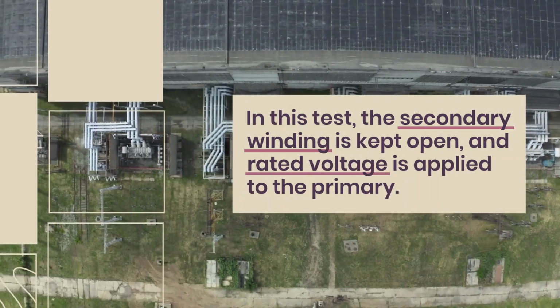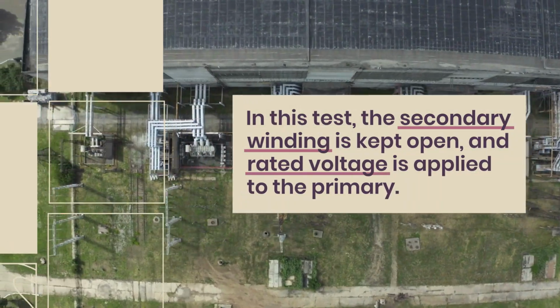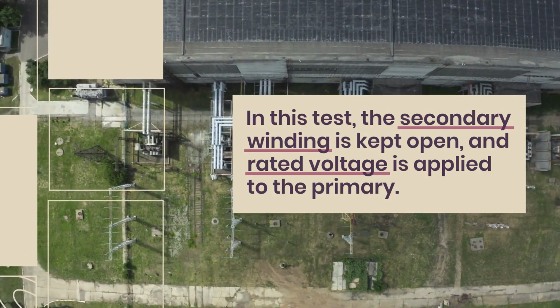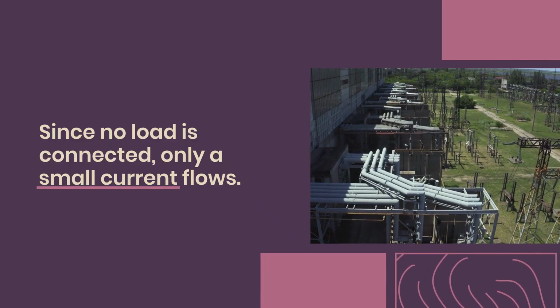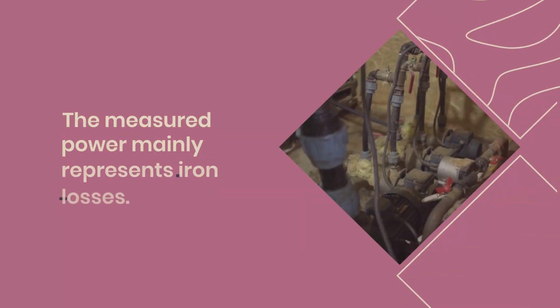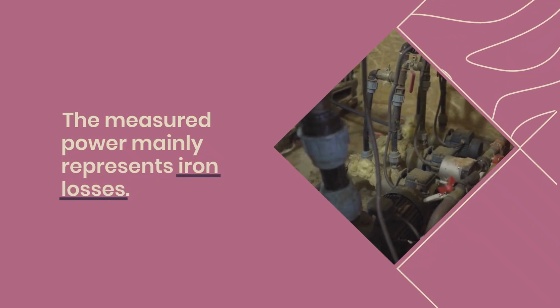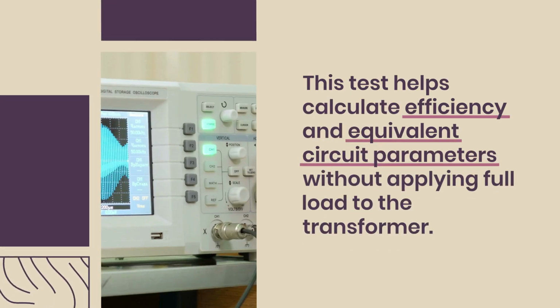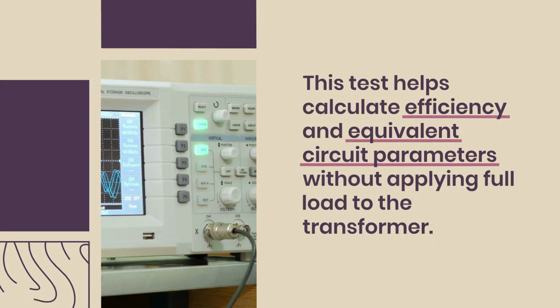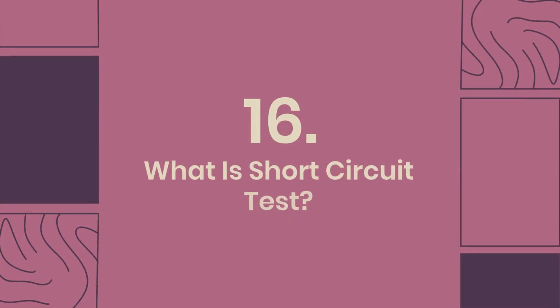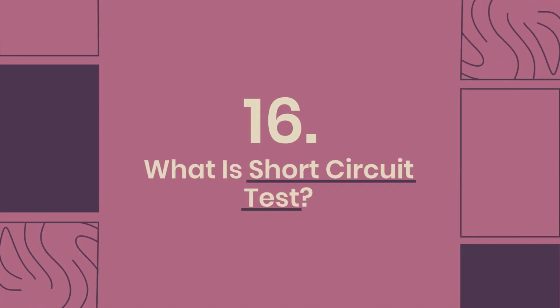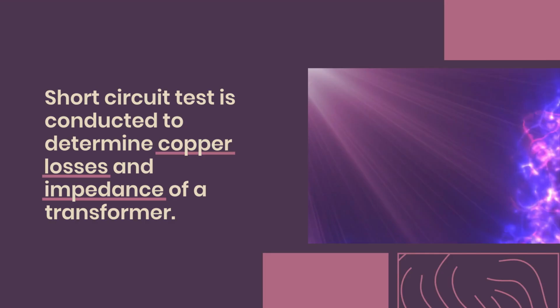In this test, the secondary winding is kept open, and rated voltage is applied to the primary. Since no load is connected, only a small current flows. The measured power mainly represents iron losses. This test helps calculate efficiency and equivalent circuit parameters without applying full load to the transformer. 16. What is short circuit test? Short circuit test is conducted to determine copper losses and impedance of a transformer.